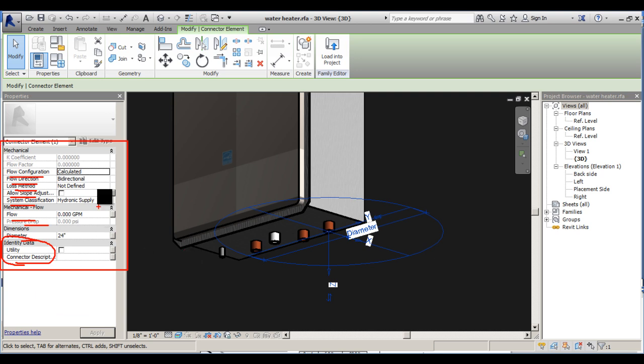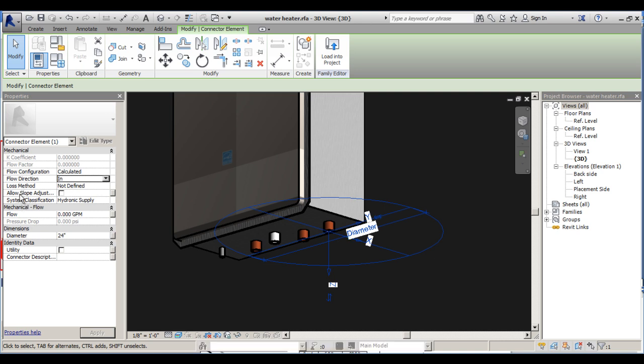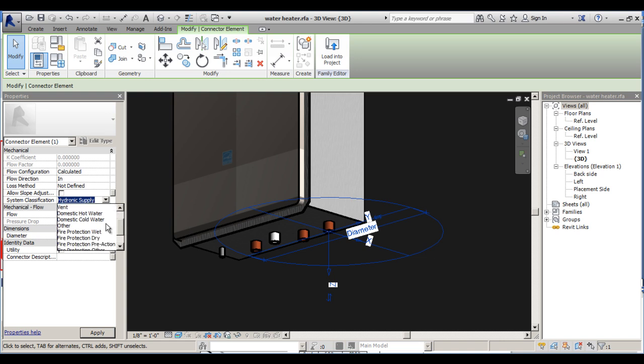Next I need to configure these parameters. Flow configuration I'll leave as calculated. Flow direction I'll change to in. Loss method is not defined. Allow slope adjustment — slope adjustments are an interesting parameter. Sometimes sloping pipes may not be allowed to connect to a family. Since we're talking about gas, we won't have sloping pipes, so I'll omit this for now. For system classification, since we're working with gas, we'll set it to other.